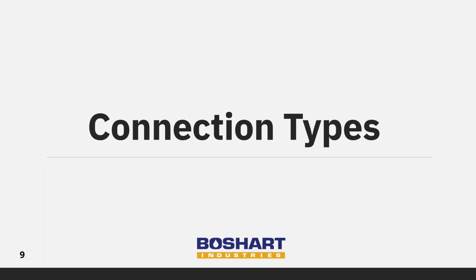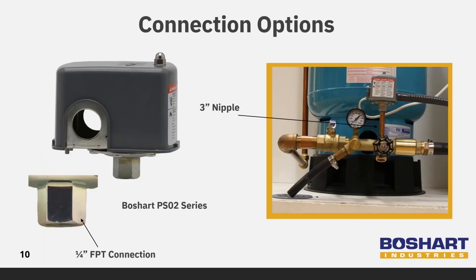Now we will look at connection types. Quarter-inch FPT connections are the most common and are ideal for installing on tank tees. They typically use three-inch nipples to lift the switch up high enough to allow the replacement of the pressure gauge without removing the switch. They can also be easily adapted to connect to tubing using barbed tube, compression, or quick connects for any pressure connection desired.